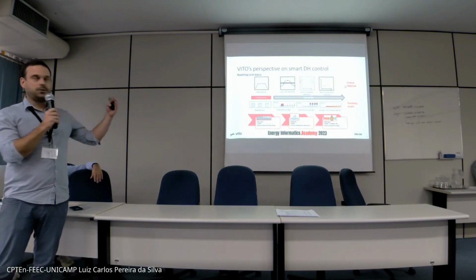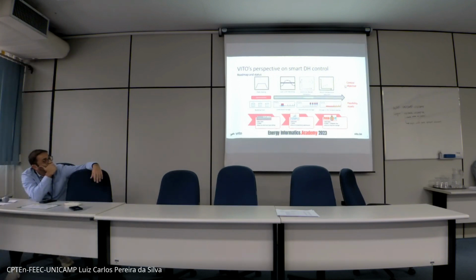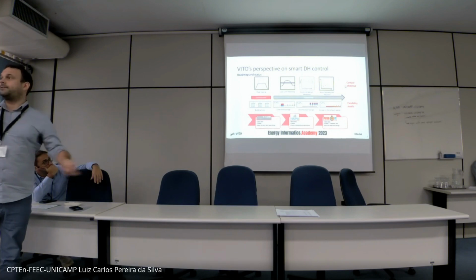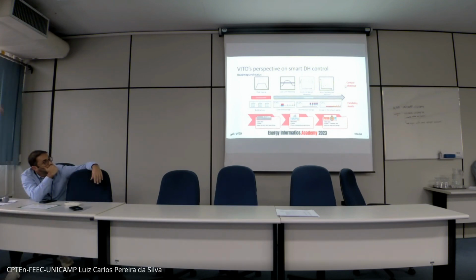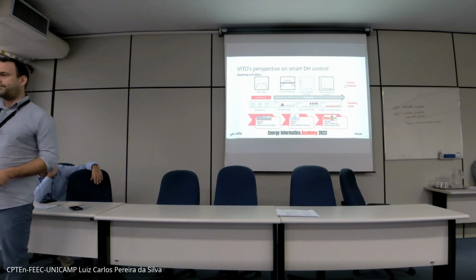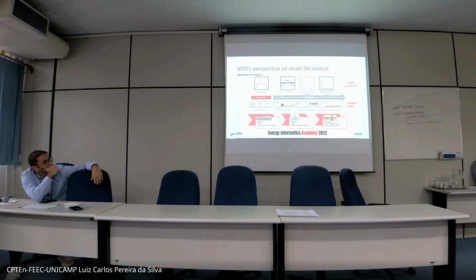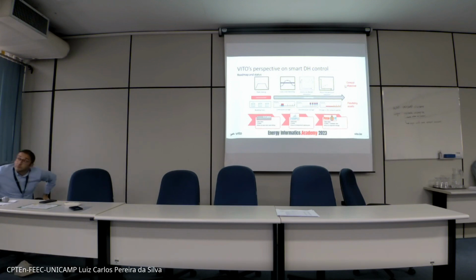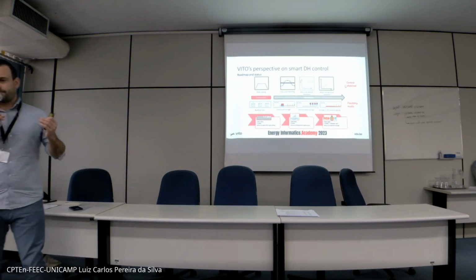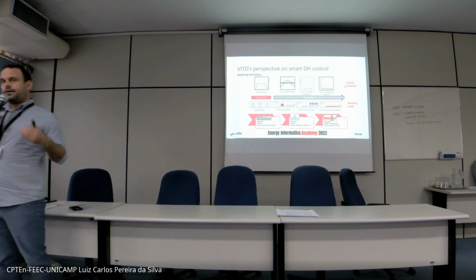In a heat network, there's a lot of flexibility available. You have the buildings themselves, which contain a lot of thermal mass that you can activate, but there's also the possibility of storages in the network, centralized or decentralized. The network itself contains a lot of water, so you can use the piping network as a storage system. Once you use this flexibility well, you can manipulate the heat demand curve of the network to achieve a certain objective.